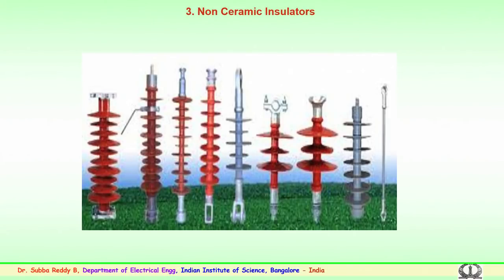So, these silicone rubber or polymeric or composite insulators are being manufactured for different voltage levels and are being used for railway traction, transmission and also for distribution purposes. So, we have briefly looked into the composition, the metal fixtures and the manufacturing of the porcelain and polymeric insulators. There are some issues, as discussed earlier.